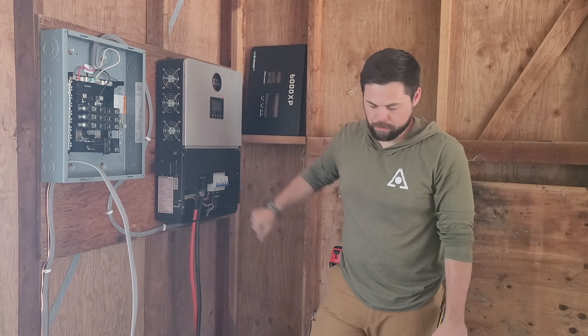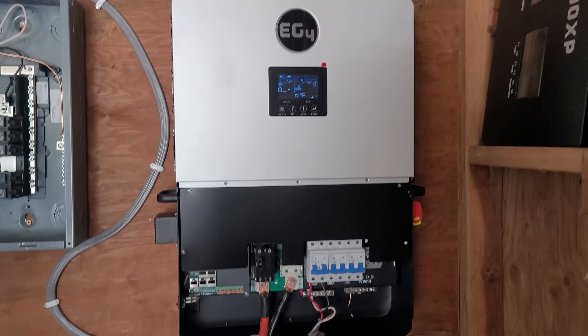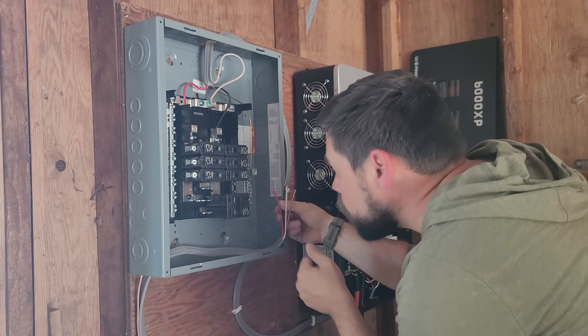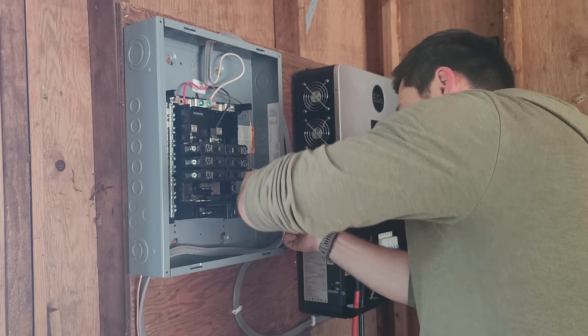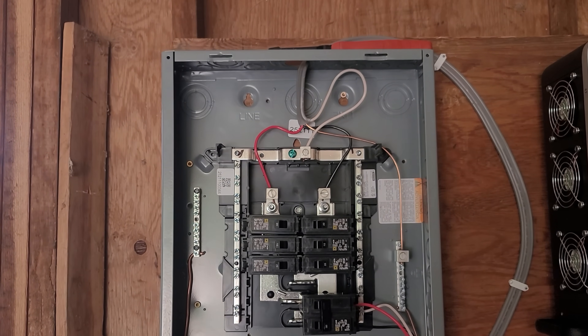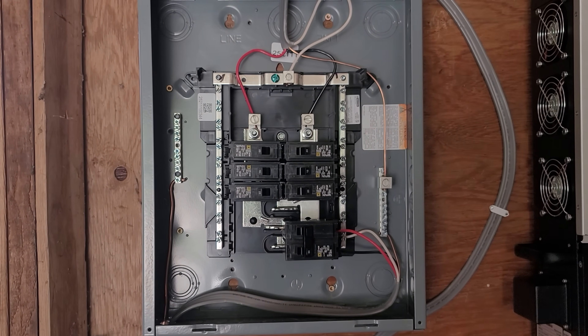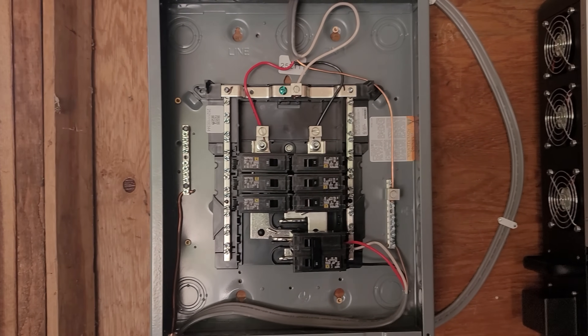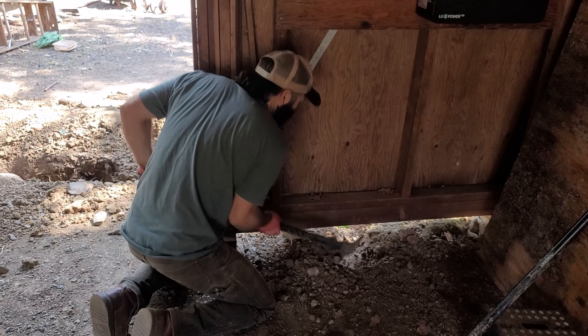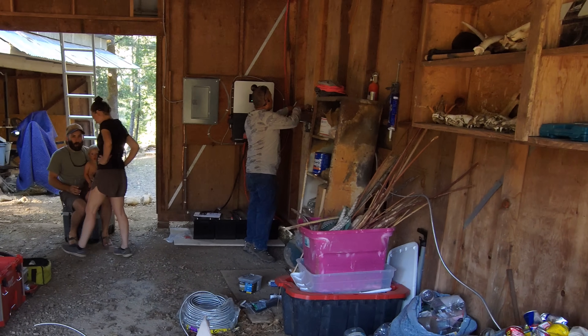It was the moment of truth to make sure this could run the inverter — and look at that! We kept everything turned off in the inverter while working on the electrical panel to make sure everything was safe. We needed to wire our subpanel to run the house over 100 feet away. It's important to keep the same colors of wires matching the same legs. On the breaker that will power the subpanel, we kept leg one as red and leg two as black. These wires come directly from the inverter. Clutch was very kind and chose to dig the trench — about 175 feet of it, completely by himself, by hand, in a ton of rocks. It was a lot of work, but it saved us a lot of time on this job.